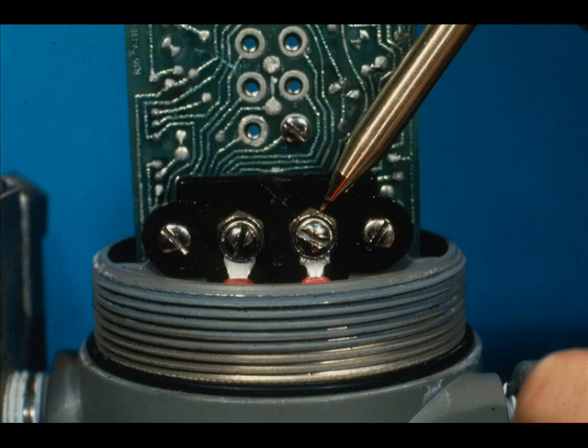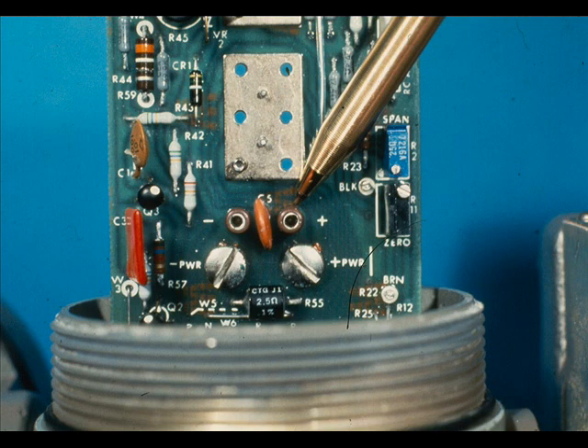The transmitters generally use a 24 volt DC power supply, but other DC voltages are permissible. The power is connected to these two terminals by the polarity indicated. The lead wires furnished with the transmitter are red and yellow. Red is positive and yellow is negative.